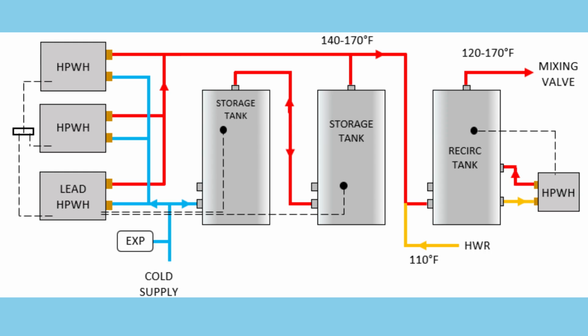No recirculation is the most efficient option when possible. Integrated systems are best for residential and small-scale applications, and always protect stratification for stable operation. Good design decisions here make the difference between a high-performing CHPWH system and one that struggles to meet demand.